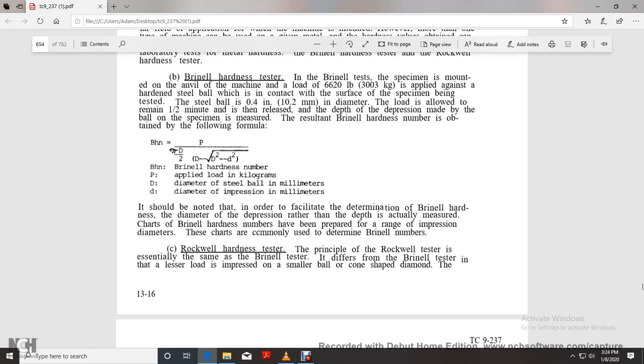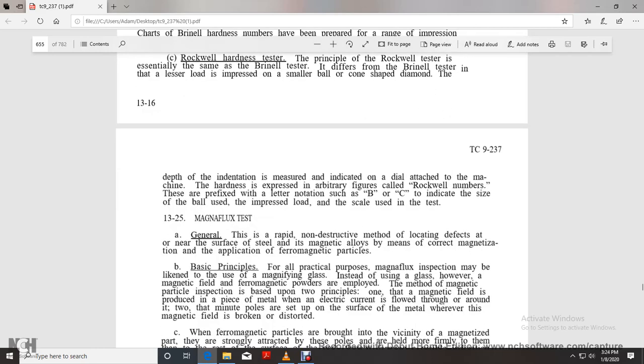The Rockwell hardness tester. The principle of the Rockwell tester is essentially the same as that of the Brinell tester, but it uses a lesser load and a smaller, cone-shaped diamond or ball as the impressor. The depth of the indentation is measured and indicated on the dial attached to the machine, with the hardness expressed as an arbitrary figure called the Rockwell number. Prefix letters such as B and C indicate the size of the ball or the impressor and the scale used for the test.